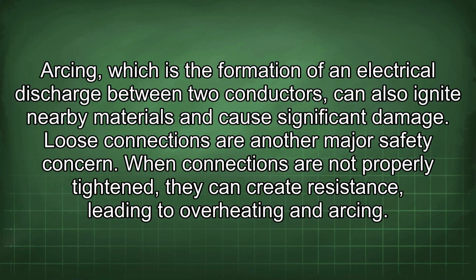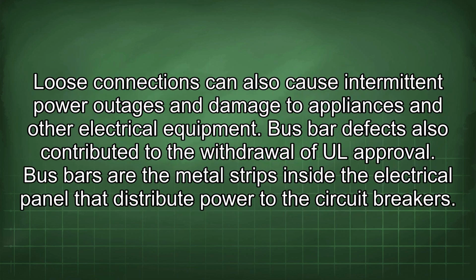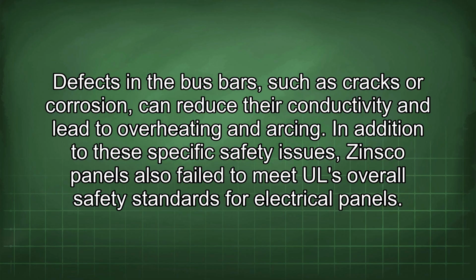When connections are not properly tightened, they can create resistance, leading to overheating and arcing. Loose connections can also cause intermittent power outages and damage to appliances and other electrical equipment. Busbar defects also contributed to the withdrawal of UL approval. Bus bars are the metal strips inside the electrical panel that distribute power to the circuit breakers. Defects in the bus bars, such as cracks or corrosion, can reduce their conductivity and lead to overheating and arcing.